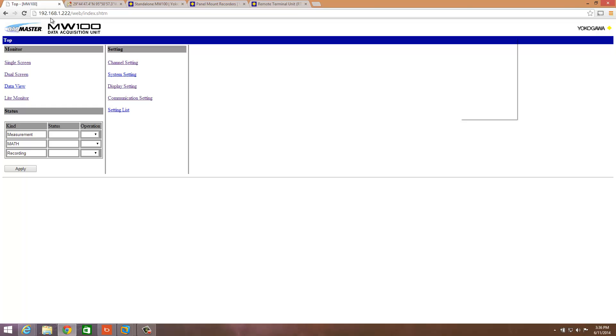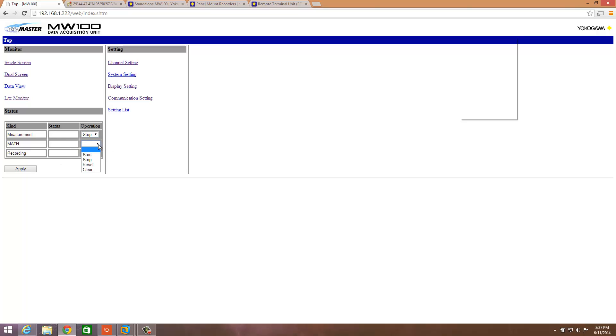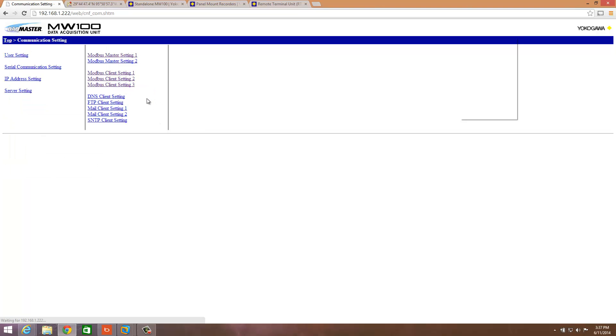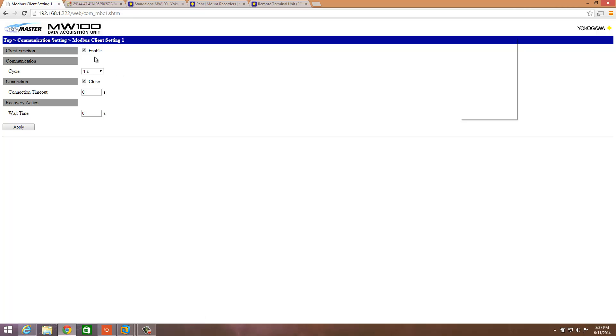So what we have here is our MW100 web-based interface. Similar to CloudGate, you can go in here and configure the unit. The items of particular interest that we're going to start with are communication settings. Make sure when you're going to configure your MW100 that everything here is set to Stop and hit Apply, otherwise you're not going to be able to make the changes necessary. We go to communication settings, and since we're communicating to the CloudGate over Ethernet to pull the GPS data, we want to go to Modbus Client. Make sure this is enabled, then set your cycle here, how fast you want to log. The rest can be set at default. Once you're done, hit Apply.